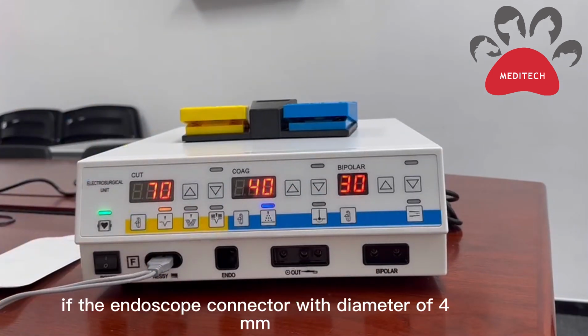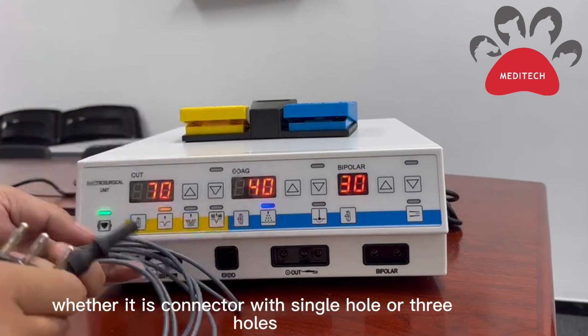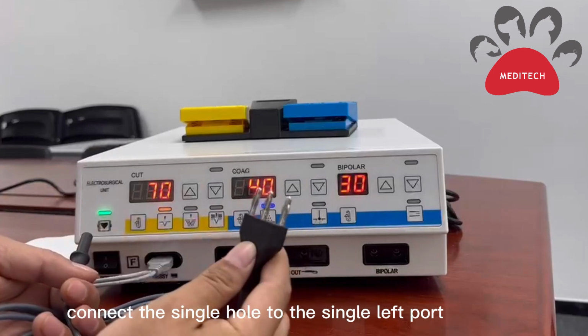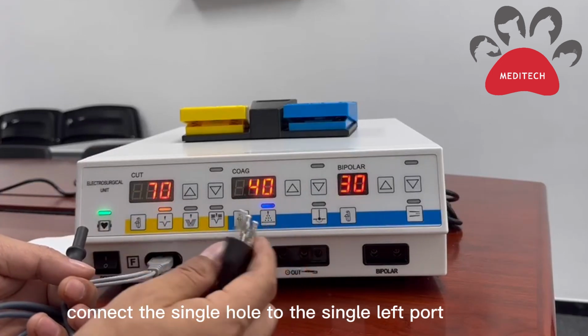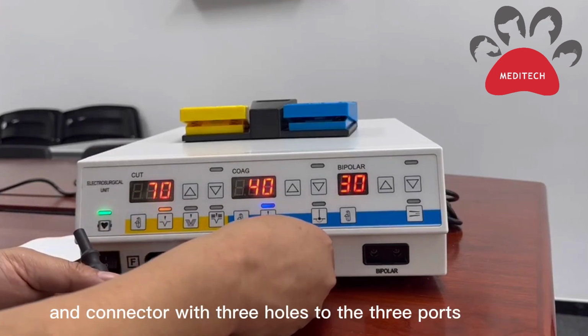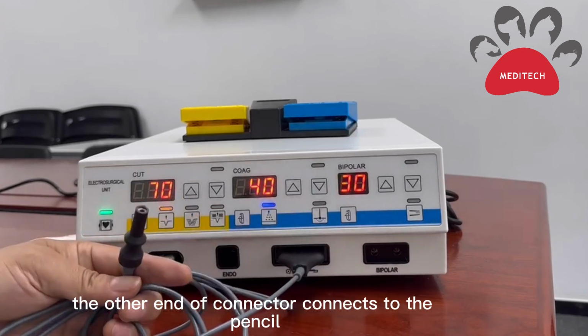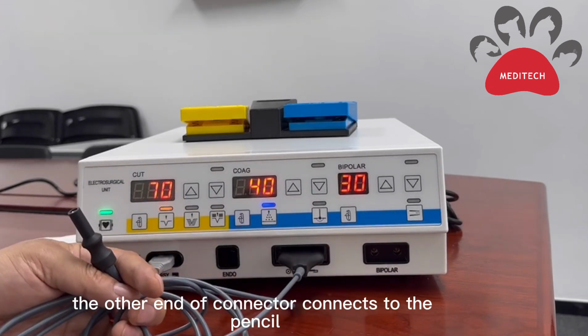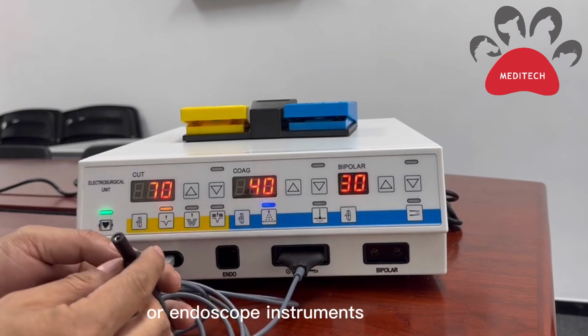If it is an endoscope connector with diameter of 4 mm, whether it is a connector with single hole or 3 holes, connect the single hole to the single left port, and the connector with 3 holes to the 3 ports. The other end of the connector connects to the pencil or endoscope instruments.